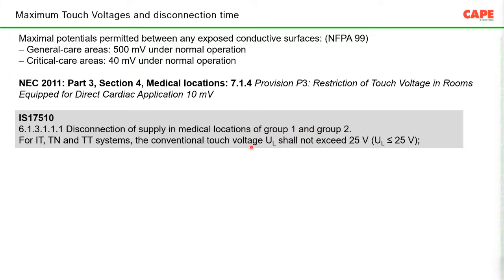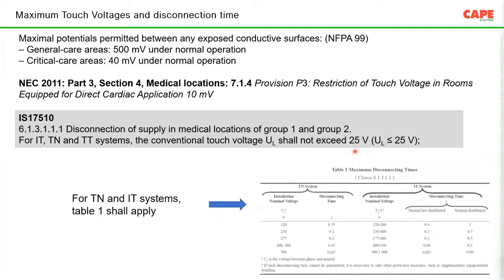The standard says the nominal touch voltage, the conventional touch voltage, shall be lesser than 25 volt. Conventional touch voltage is not in normal condition. This is in a fault condition. That means probably you have a faulty equipment or a faulty electrical wiring. Under a fault condition, the maximum allowed touch voltage in group 1 and group 2 medical locations is lesser than 25 volt, or before the voltage reaches 25, we are supposed to disconnect the supply.